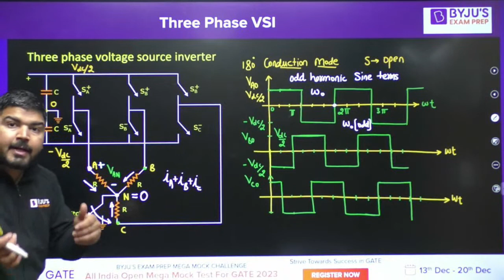So the sum of these currents, IA plus IB plus IC, will be equal to IN, because they contain the triplen harmonic also. The switch is closed. If the switch is closed and they contain triplen harmonic, then the sum of the triplen harmonic will not be 0. This sum will be equal to this current IN, and this will not be 0 this time, because their triplen harmonic components will be added, and that current will flow through the switch. The switch will contain only the triplen harmonic current.